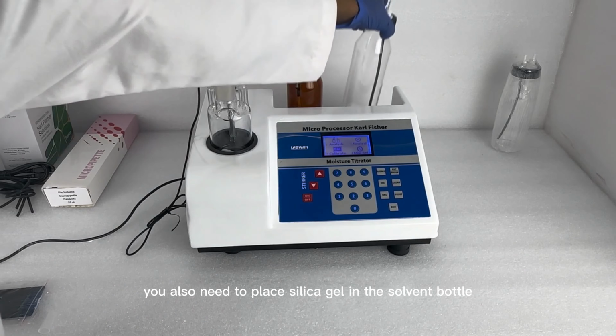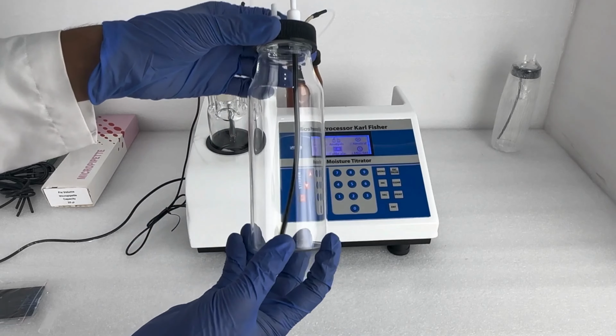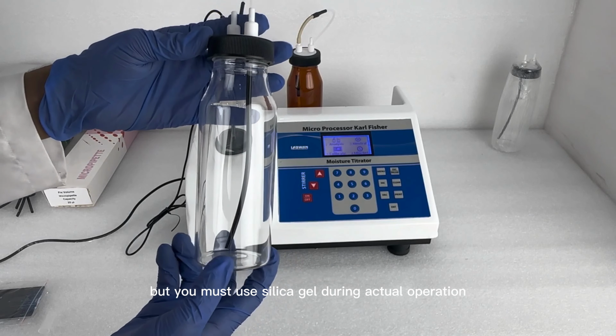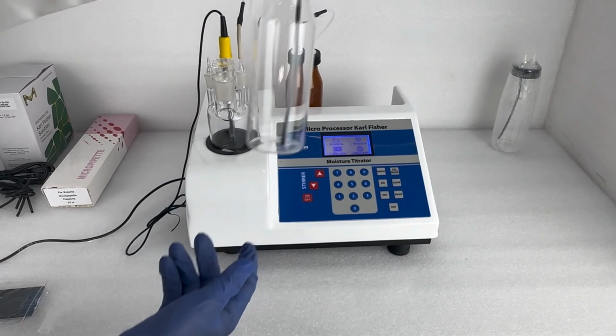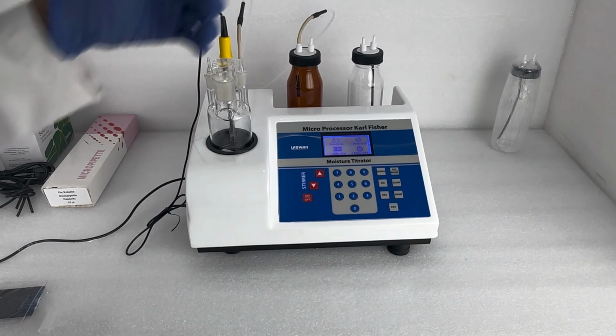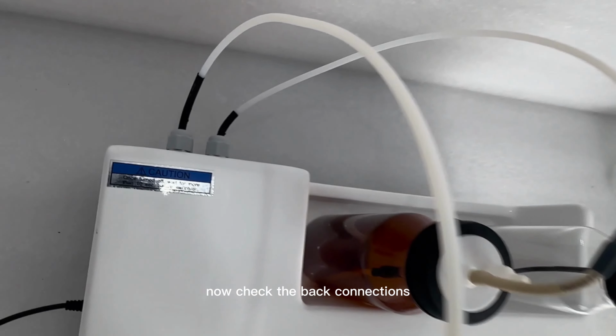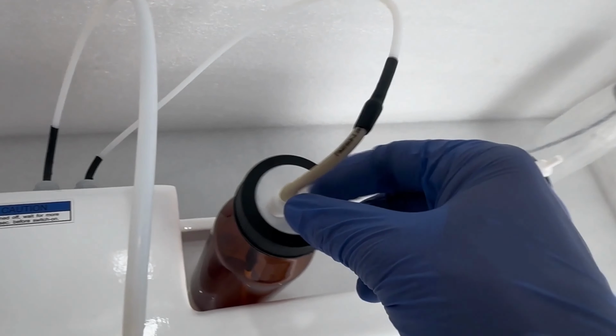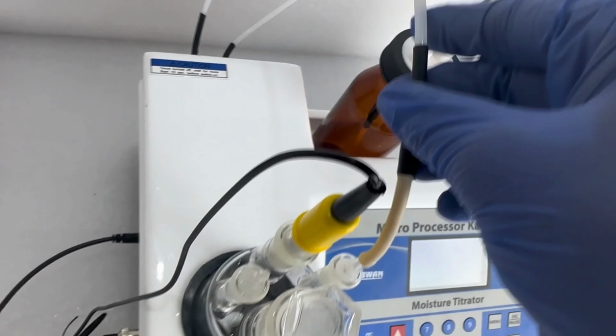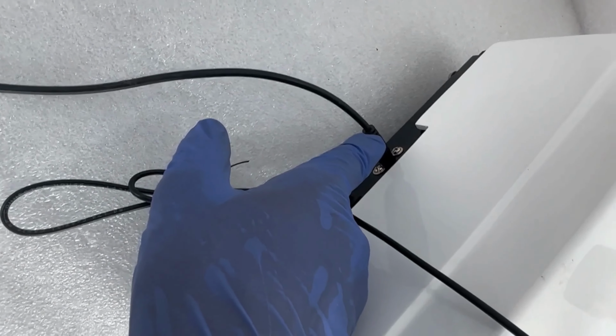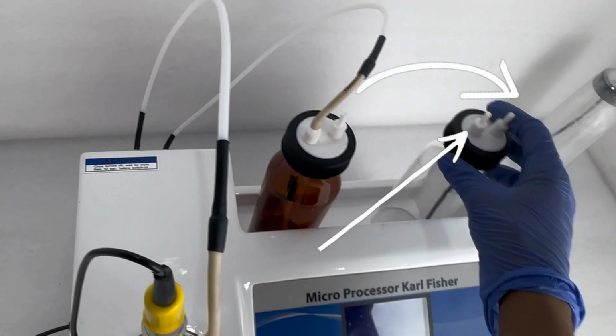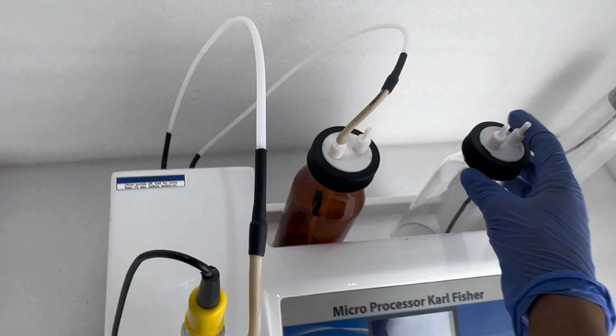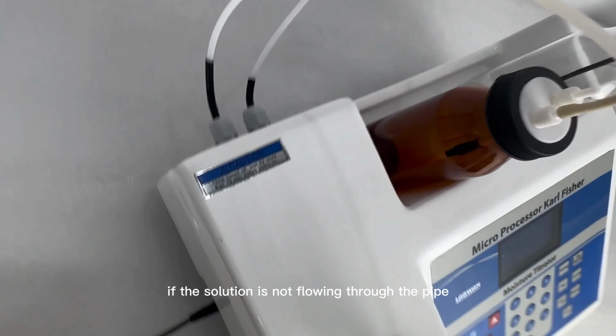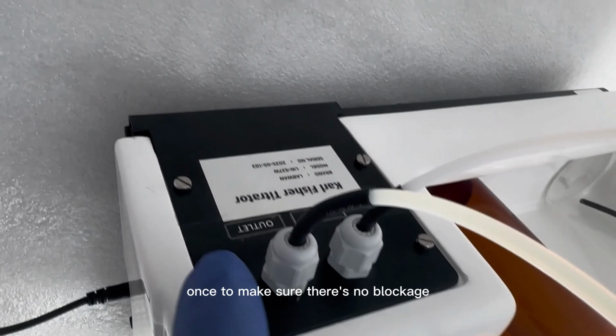You also need to place silica gel in the solvent bottle to get accurate results. In this video, I'm not using it, but you must use silica gel during actual operation. Now, check the back connections, the pipe from the reagent bottle, and the electrode cable, should be connected as shown. When the silica gel bottle is attached, connect it to the support base, as shown in the video. If the solution is not flowing through the pipe, open the pipe from the back once to make sure there's no blockage.